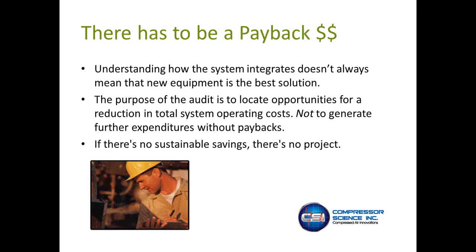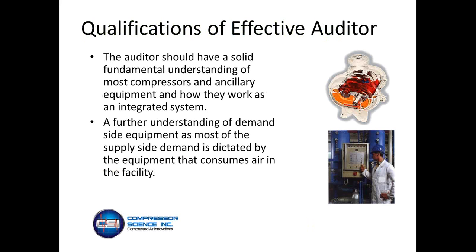We've gone into systems where rebates were given and machines were put in, and we find out that the VFD is now running flat out because the items out in the plant weren't resolved to begin with. So if there's no sustainable savings, there should be no project.